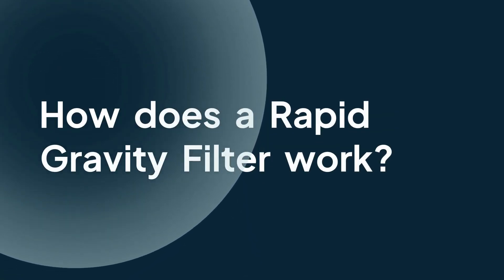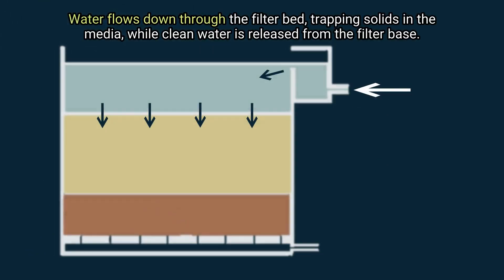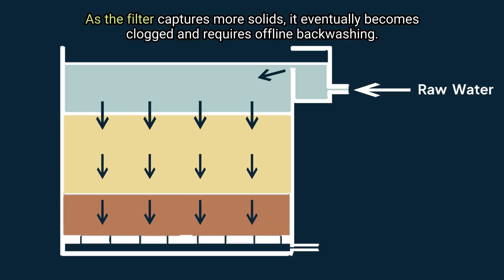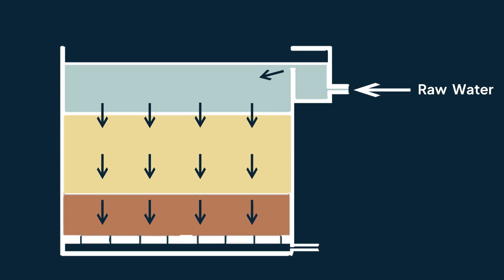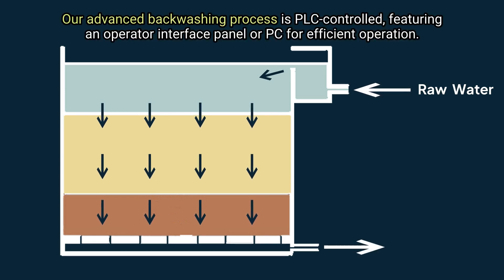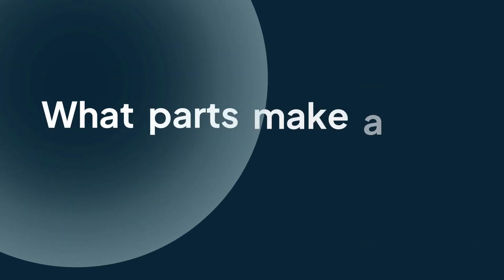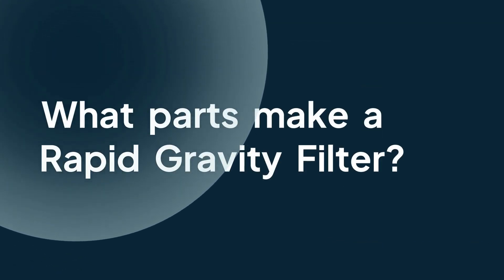How does a rapid gravity filter work? Water flows down through the filter bed, trapping solids in the media while clean water is released from the filter base. As the filter captures more solids, it eventually becomes clogged and requires offline backwashing. Our advanced backwashing process is PLC controlled, featuring an operator interface panel or PC for efficient operation.